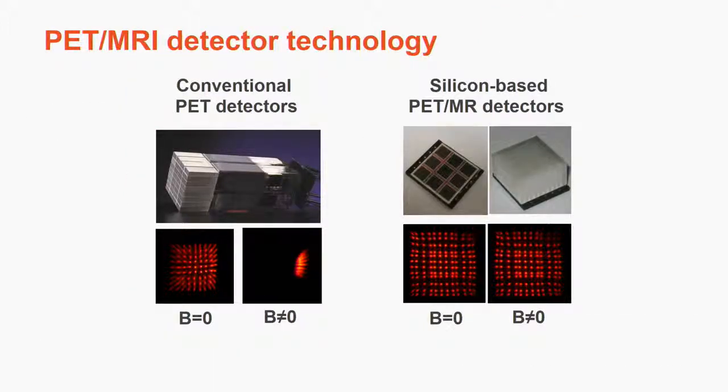The other thing I mentioned earlier on is the ability to do multimodality imaging, and so when we use these silicon photodetectors, they're highly immune to magnetic fields, and so that's what's primarily given us the capability to do PET-MR systems, whereas the more conventional photomultiplier tube-based detectors are highly sensitive to magnetic fields. So that's where that development has primarily come from.